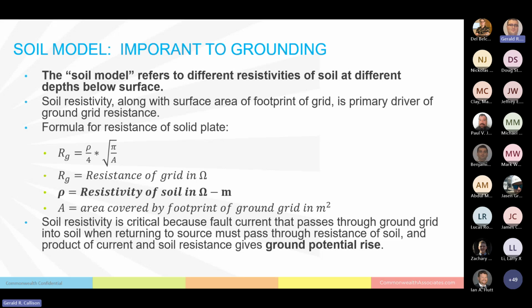Now, soil resistivity is critical because we've got this ground fault current in the station, and it passes through the ground grid into that soil, through that grid-to-soil interface, on its way back to the source. That soil has a resistance defined by the resistivity, and the ground fault current going through the soil times the resistance of the soil gives you the ground potential rise, which is the potential of your ground grid during a fault with respect to remote earth. So the soil model is central to the performance of your ground grid.